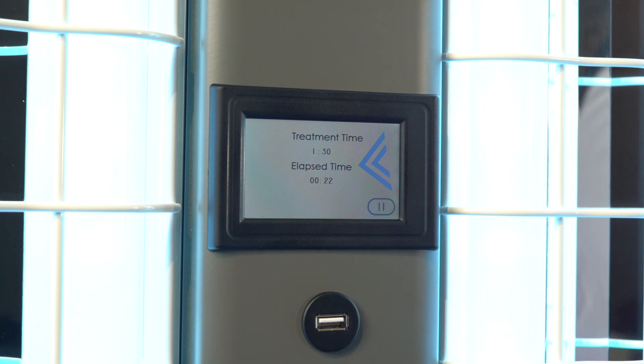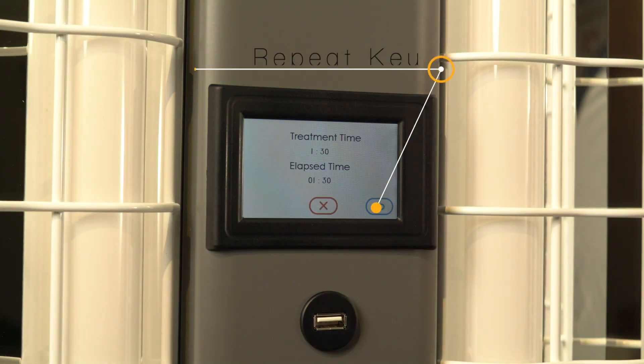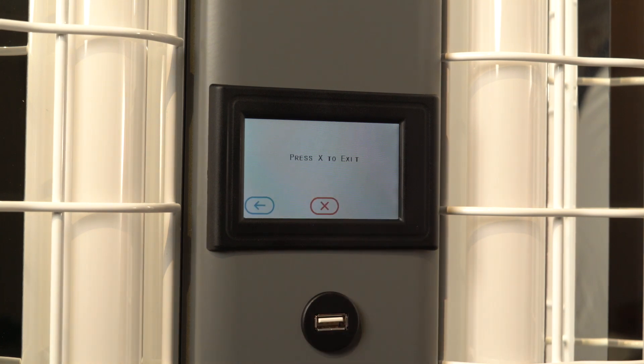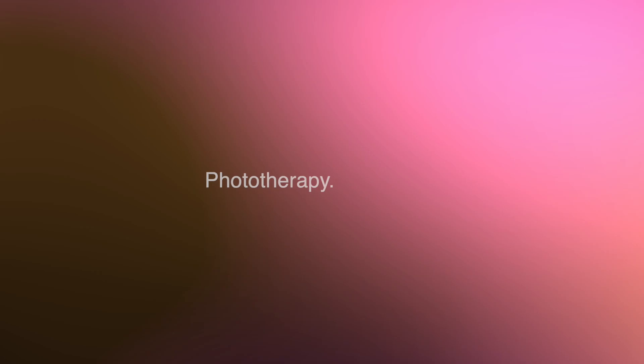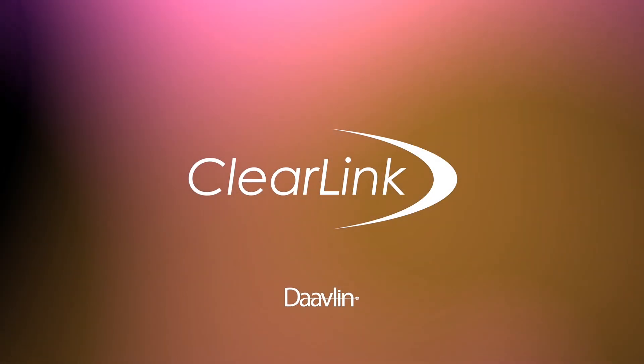Once the time that you entered has elapsed, the lamps will shut off, the screen will display your delivered treatment time, and the system will record that information plus the date and time of the treatment in its record. If it is necessary to treat several areas of your body—what is called a treatment sequence—simply press the repeat key after each segment of the treatment, and the exact time will be repeated up to three times. After your treatment has finished, press the red X button and the device will go into its sleep mode. Congratulations, you have successfully completed a treatment with the Daavlin ClearLink controller.